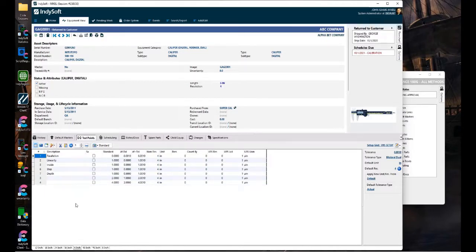So in this particular scenario where I'm basing something on size, I can create a generic equipment template, so that when I create a new gauge from a template using this button right here, the instrument gets created. It doesn't have a manufacturer model number, just maybe some generic description information, type, subtype, that kind of thing, and a series of the test point tabs across the bottom.